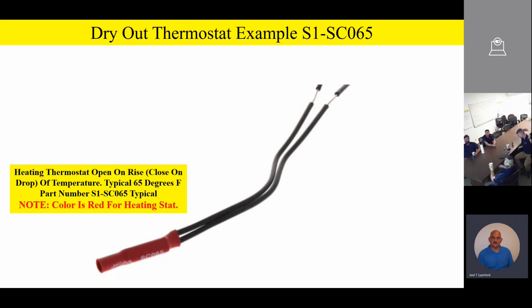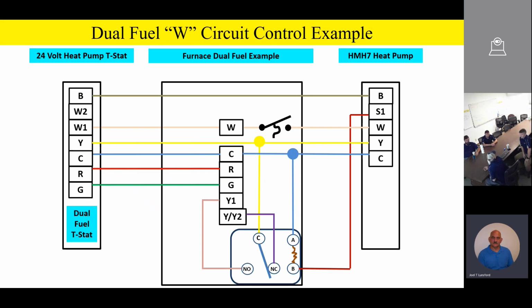And again, this is something we've just added within about the last week. If you're doing dual fuel, we're going to recommend that you use this. And again, mount it on the suction line of the indoor coil, and then you're going to wire it into the circuit. Here's an example right here. So basically all we're doing with that little construction thermostat, if you look at my cursor closely, is we're just breaking the W wire from the outdoor unit to the indoor unit.